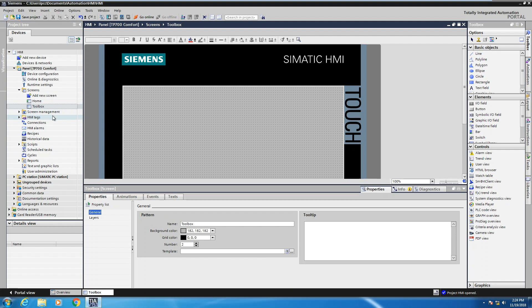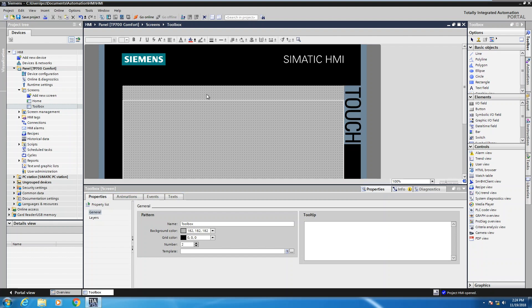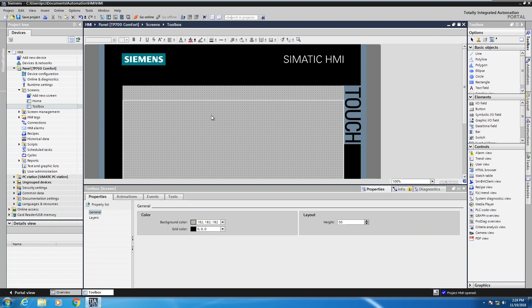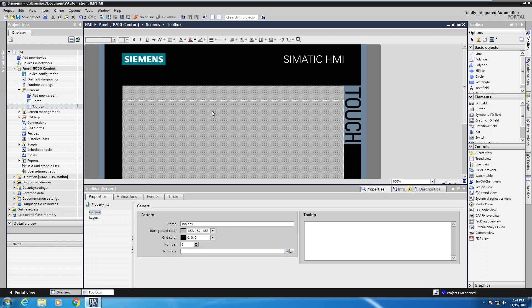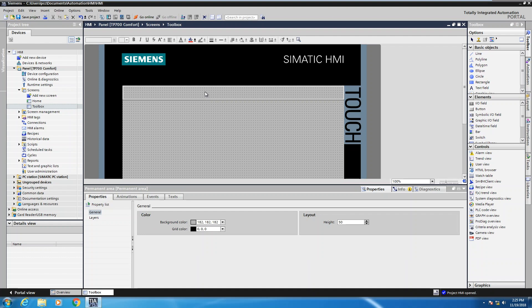Now with the two screens created, the next thing I'd like to do is establish my fixed window area. I highly recommend you do this at the start of your HMI project — it makes things much easier. Position your cursor up at the top of your toolbar, because there's only one area where the fixed window screen can be located. I'll drag down a little bit, and now you can see two distinct areas: the area at the top is the fixed window, and the area below is the template area. The fixed window area shows up on every single screen in your application, while the template area is utilized based on whether you choose to use a template.